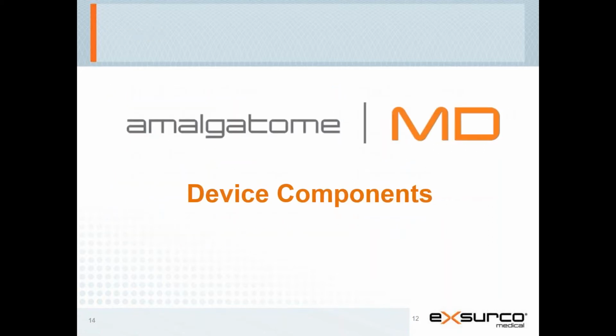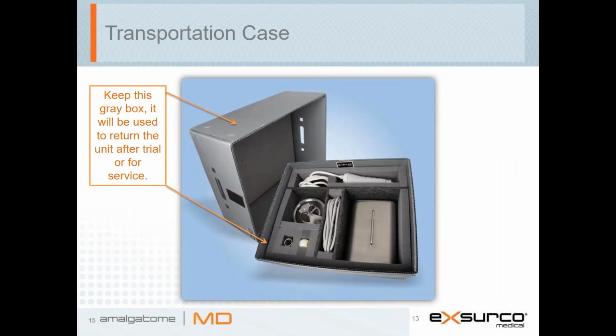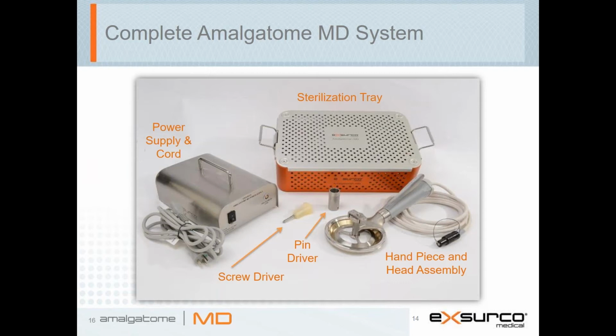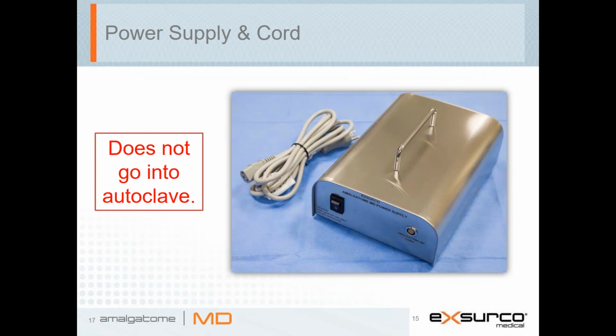Device components. Transportation case. Do not discard this case. It is the only form validated for shipping. Use this case to return to Exsurco for any service or repair. Complete Amalgatome MD system. Power supply. This does not go into the autoclave. Care should be taken not to drop or damage. Do not plug any other power sources into the power supply for use for any other purpose.